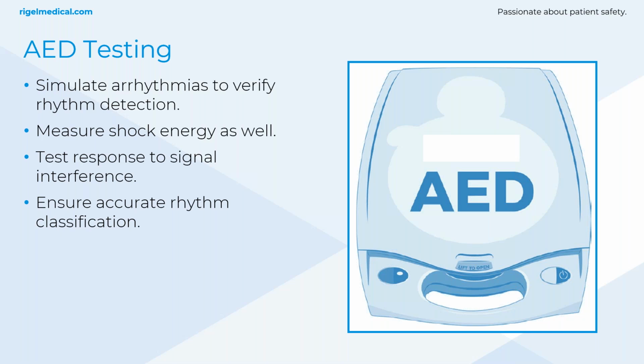So first, what we're doing is simulating different cardiac arrhythmias, just like the real thing. What a defib analyzer is doing is simulating all the different electrical signals that you'll see in the heart, and it's going to feed those ECG waveforms into the AED to see how it reacts. Is it going to correctly identify ventricular fibrillation as a shockable arrhythmia? Is it going to tell the user that it's detected asystole or pulseless electrical activity correctly? And is it going to tell that there's no shock advised, and there's no option to perform that shock even? That's what it should be doing. But can it also tell the difference between a fast but safer rhythm and ones that are more life-threatening? So it needs to do all of those things accurately, and we're testing that response.